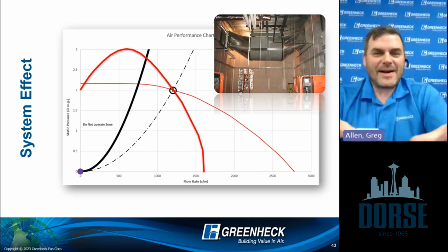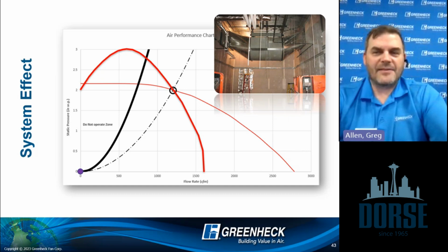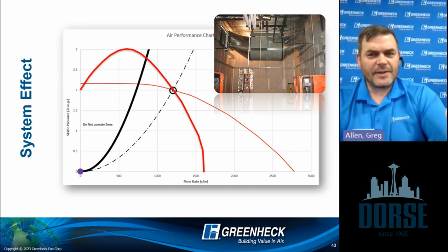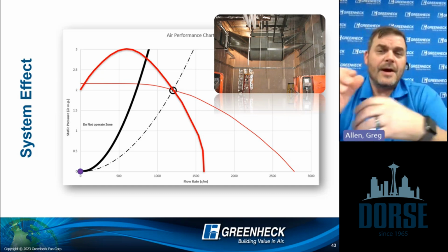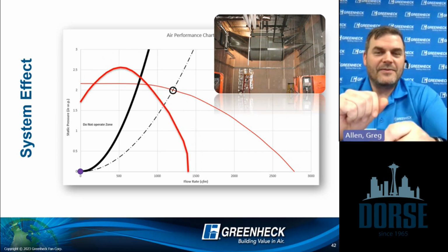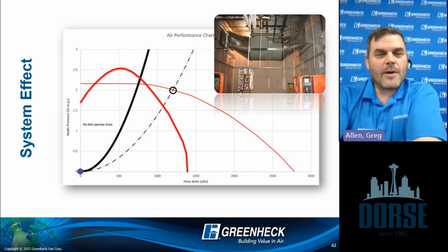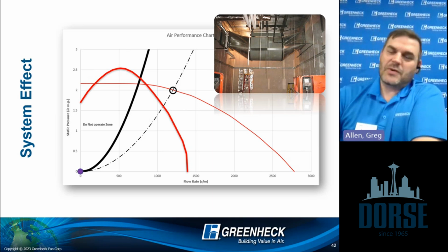So I kind of wanted to get to this point where I showed you that the best selection of a fan can be affected by final installation. I don't think that surprises anybody. But the surprise here comes at how much it can affect that fan's capability to move air. And I wanted to throw it all back onto a fan curve, which is where we started.